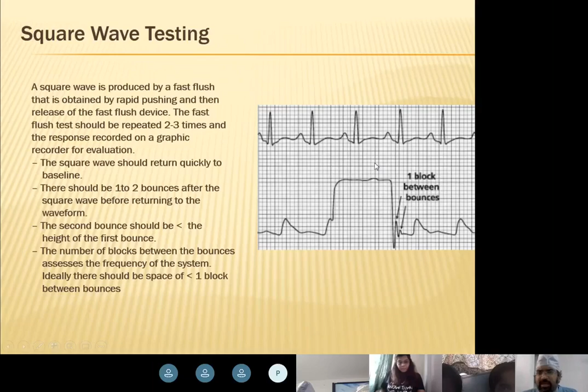Again, do the fast flush test. When we do the fast flush test, you see very high oscillations. See, this has gone up. It has given 300 pressure, come down, then 1, 2, and 3. There are 3 bounces. And if you look at the second bounce, it is almost equal to the first bounce. This is called underdamping.